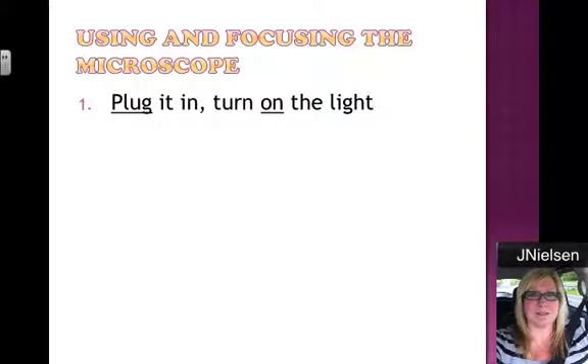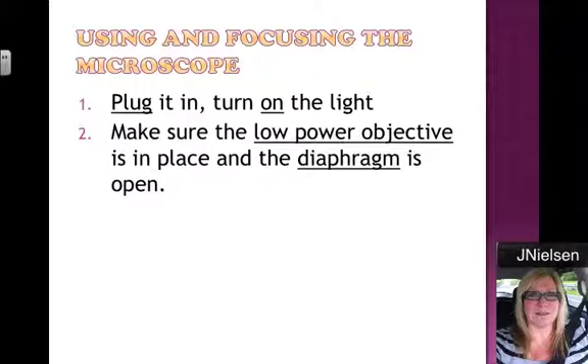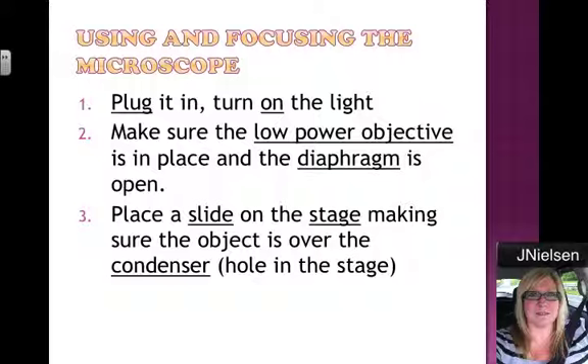When we take the microscope out, we want to plug it in and turn on the light — there's a little on-off switch. Make sure that the low power objective is in place, that's the smallest one, and that the diaphragm is open. You'll know if the diaphragm is open or closed because you'll see how much light is coming through the stage. Place a slide on the stage, making sure that the object is over the condenser — that's the hole — so that the light can pass through it. Then use the stage clips to hold the slide in place.